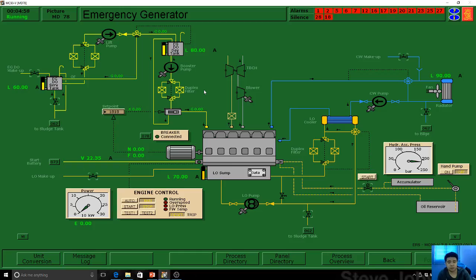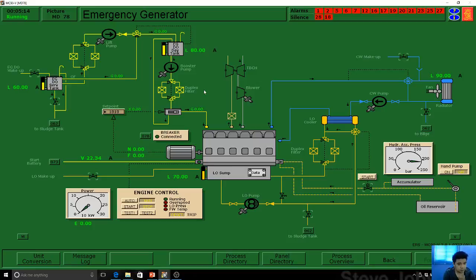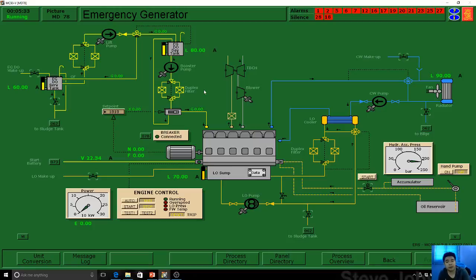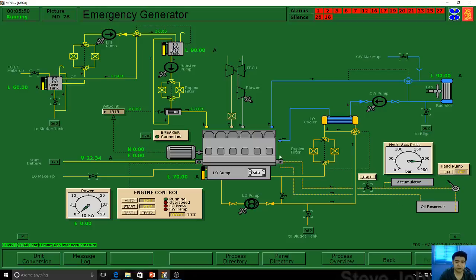The Kongsberg system has two systems of starting. One is start battery, using the 24-volt battery supplied on the emergency switchboard. The other is a hydraulic accumulator. Electricians typically use a hydrometer to test the battery. The hydraulic accumulator is an ordinary pump — you just pump it. There's a switch-on button for the accumulator, which is an oil reservoir hydraulic starter.